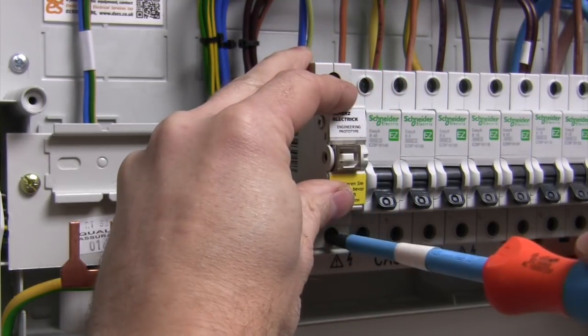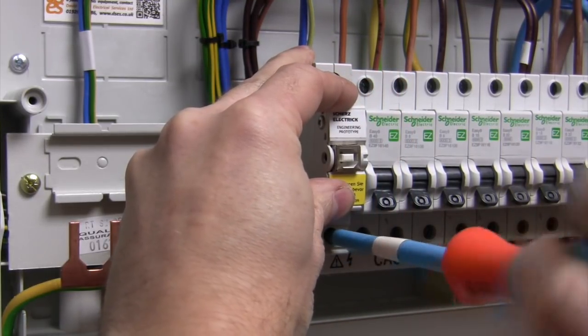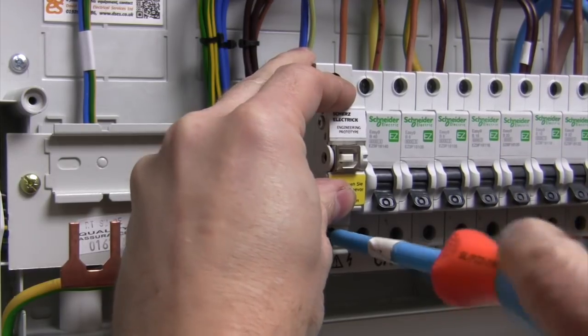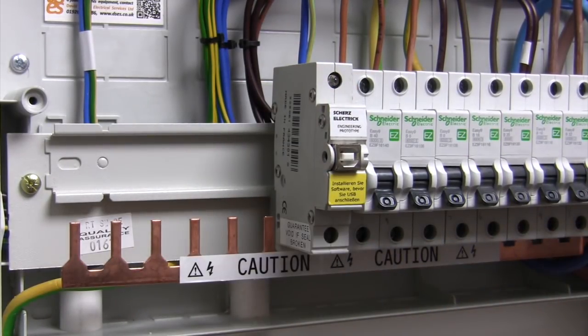It's the size of a standard MCB, and the manufacturer claims it'll fit into 93% of 16th edition or later consumer units. With the power off, connect it to a spare way on the busbar and hook up the neutral and earth fly leads.